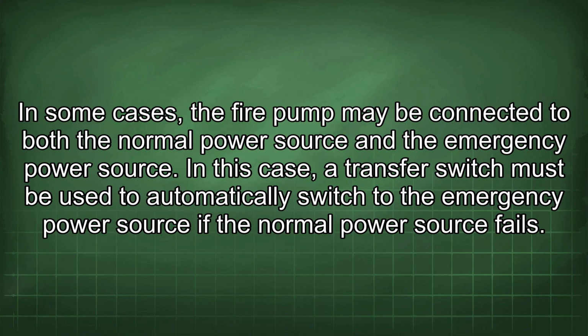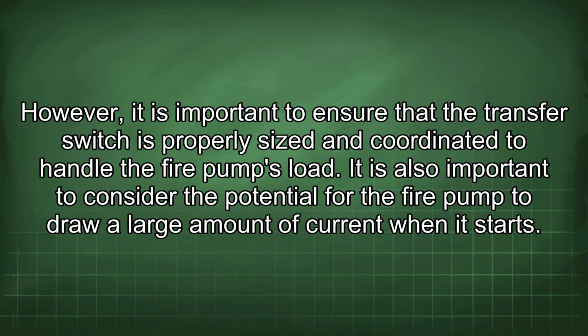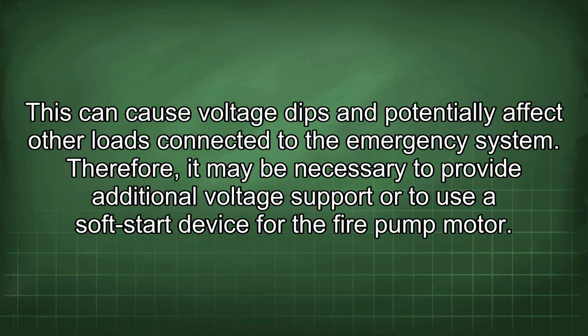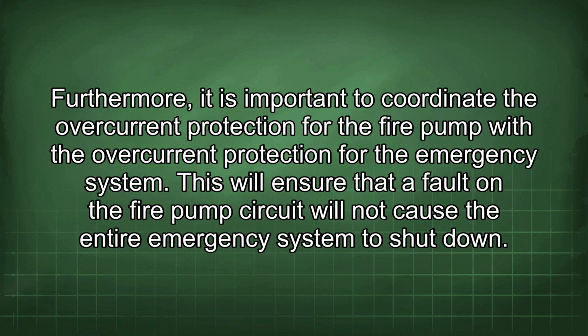In some cases, the fire pump may be connected to both the normal power source and the emergency power source. In this case, a transfer switch must be used to automatically switch to the emergency power source if the normal power source fails. However, it is important to ensure that the transfer switch is properly sized and coordinated to handle the fire pump's load. It is also important to consider the potential for the fire pump to draw a large amount of current when it starts. This can cause voltage dips and potentially affect other loads connected to the emergency system. Therefore, it may be necessary to provide additional voltage support or to use a soft start device for the fire pump motor. Furthermore, it is important to coordinate the overcurrent protection for the fire pump with the overcurrent protection for the emergency system. This will ensure that a fault in the fire pump circuit will not cause the entire emergency system to shut down.